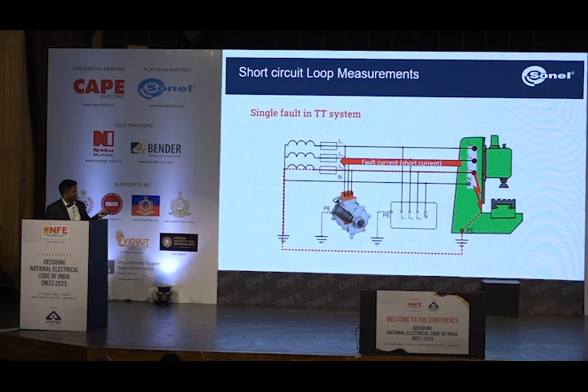Now, in any design that we have, there is a protective device installed by default - let it be your MCB, RCD, whatever it is. The purpose of this protective device is to ensure that it trips. The standard says you have to do the testing twice a year, and keep a record of this for 2 years, which means in a 2-year backup you should be testing this about 4 times and keeping the record.